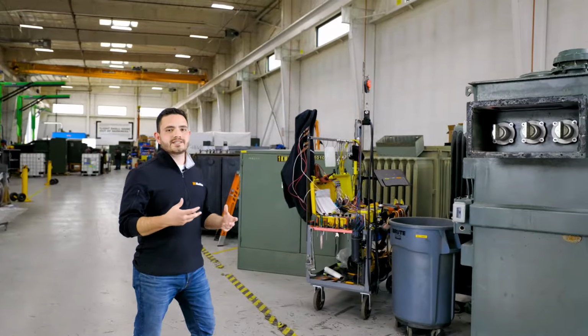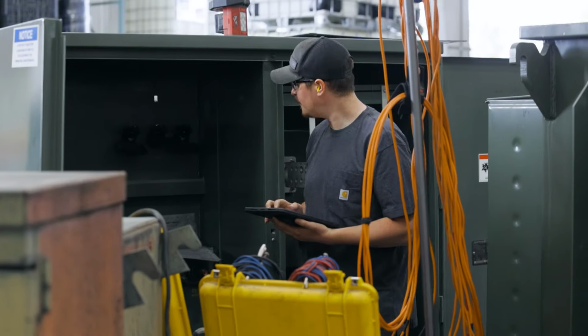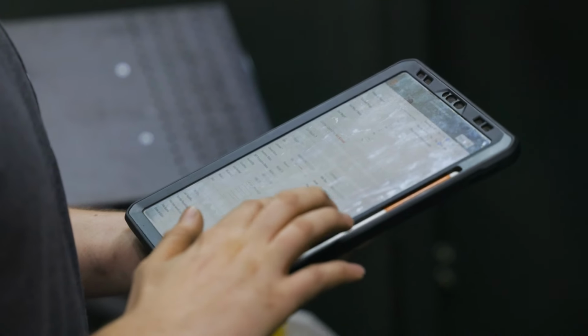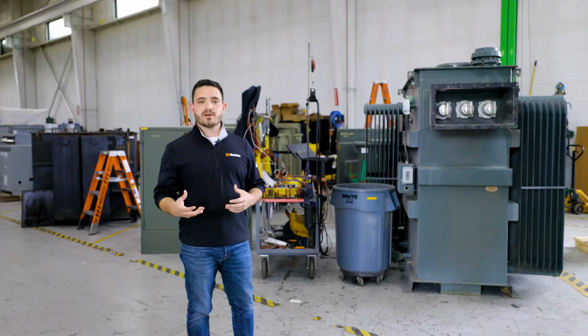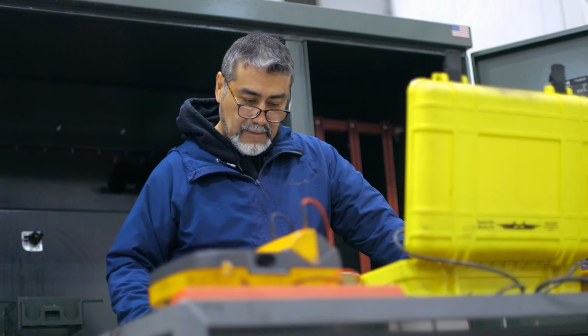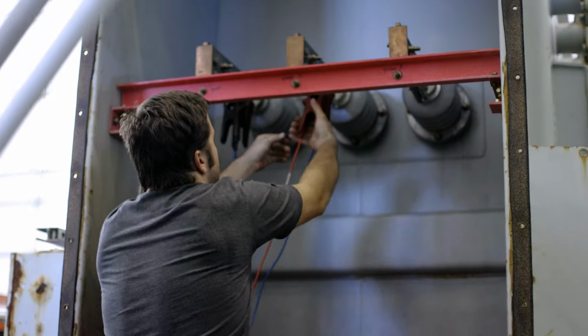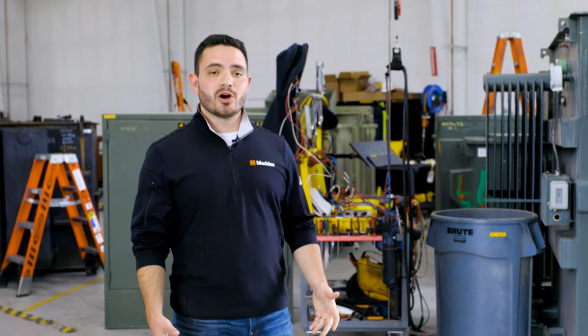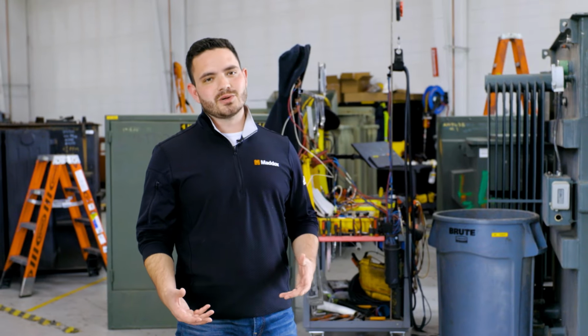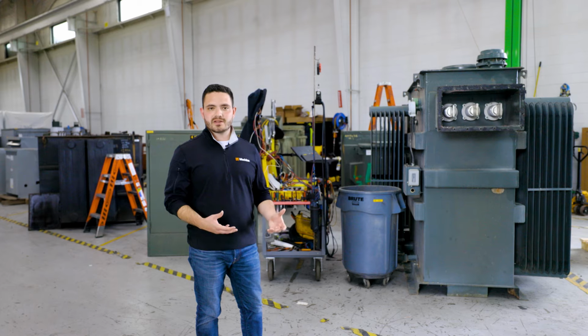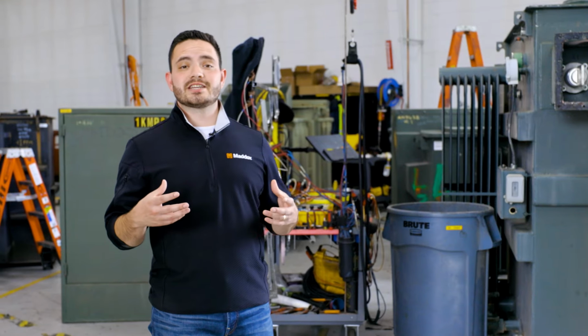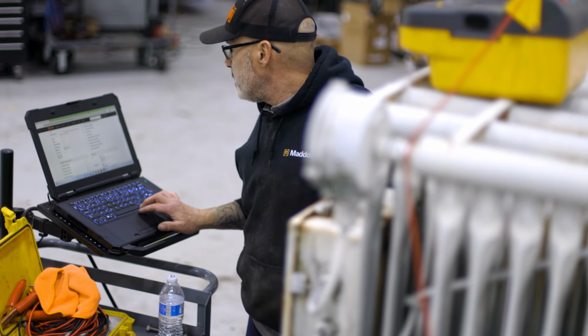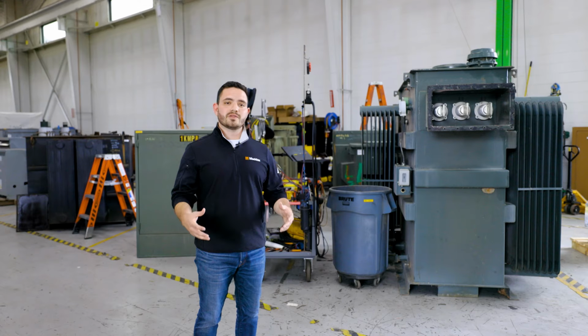Here, our inventory technicians will take pictures, dimensions, and import all the nameplate data into our system. And they'll also perform some preliminary testing, including Megger, TTR resistance, and DGA. Obviously, what we hope for is a clean bill of health, but if we don't get that, we do know what will need to be fixed on the transformer. All this information is meticulously cataloged in our inventory system, so the salespeople know what's available to sell, at what lead time, and they can share that information with the customer with the click of a button.